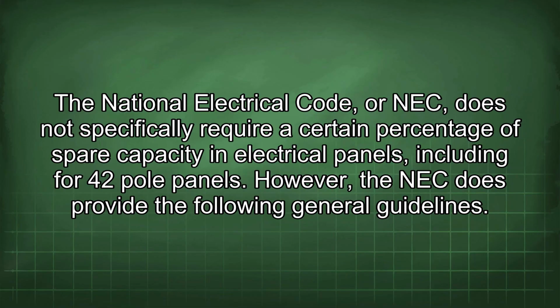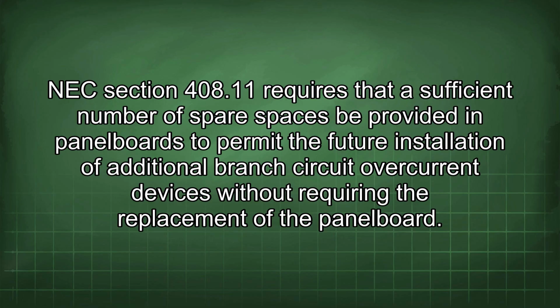The National Electrical Code, or NEC, does not specifically require a certain percentage of spare capacity in electrical panels, including for 42-pole panels. However, the NEC does provide the following general guidelines. NEC Section 408.11 requires that a sufficient number of spare spaces be provided in panel boards to permit the future installation of additional branch circuit overcurrent devices without requiring the replacement of the panel board.